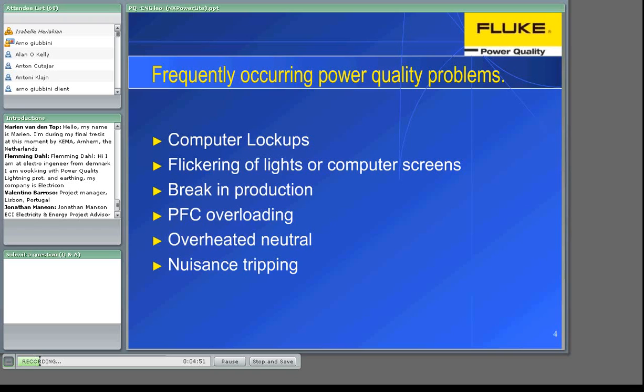Or the neutral overheating. In the past, installers used half-sized neutral conductors. The triple harmonics add up in the neutral. Some cases in commercial buildings show neutral currents between 150 and 200% of the phase current, resulting in an overheating of the neutral conductor. Nuisance tripping. Residual current breakers operate by summing current in the phase and neutral conductors. Now, the presence of leakage current harmonics flowing through the installation capacities can generate unwanted breaker tripping.